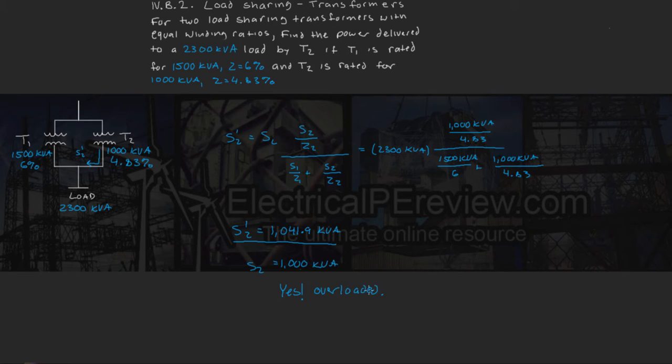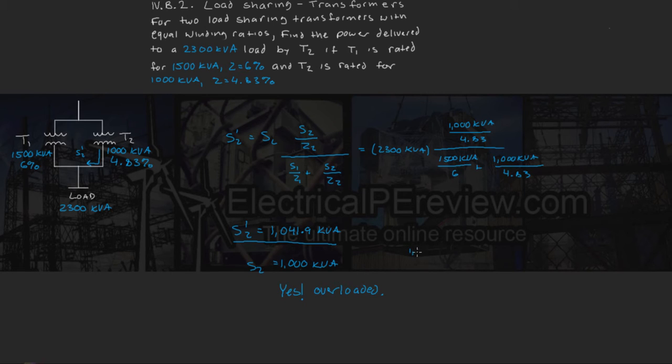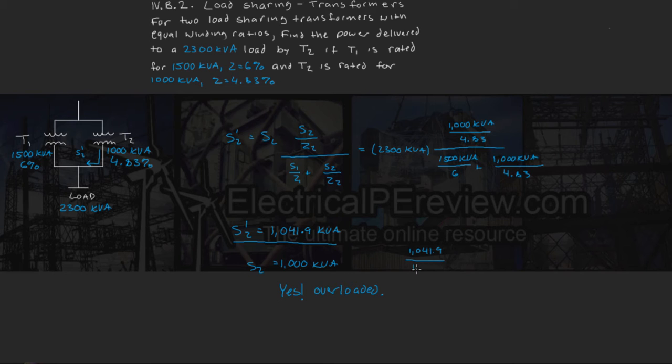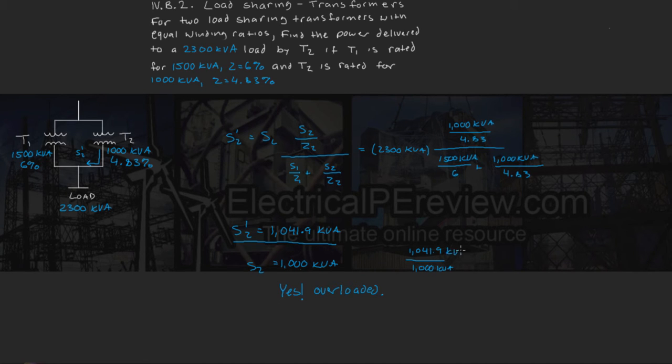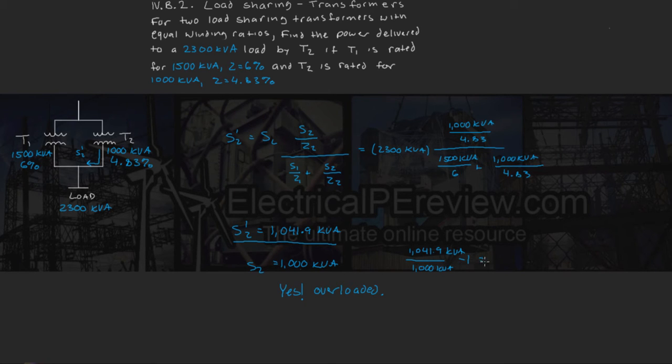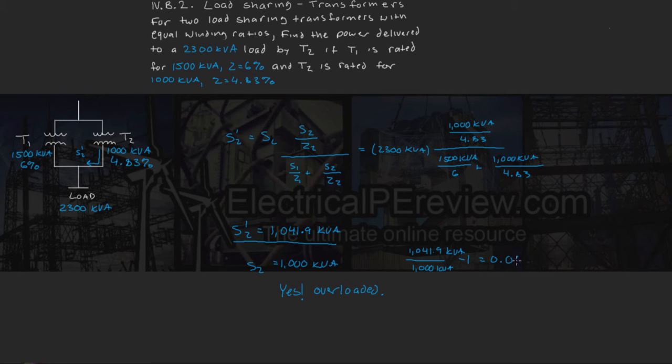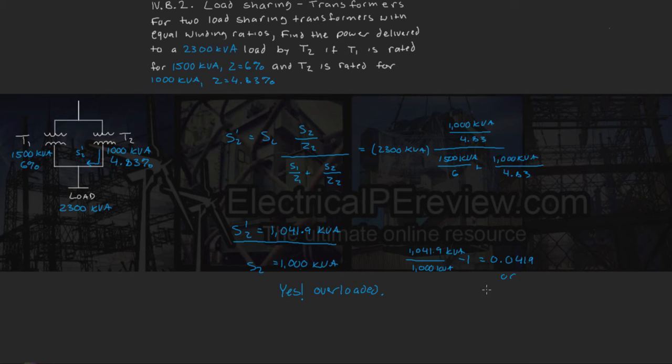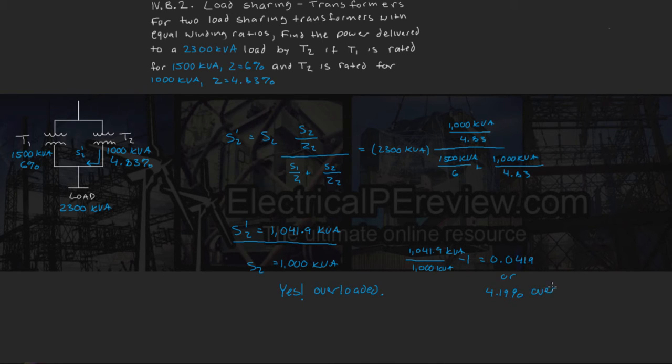Now if we're asked to find by how much, we can take the percentage of the overload as 1041.9 kVA divided by 1000 kVA minus 1 equals 0.0419, or that's the same as 4.19% overloaded.